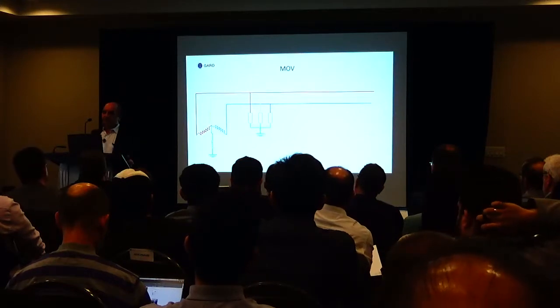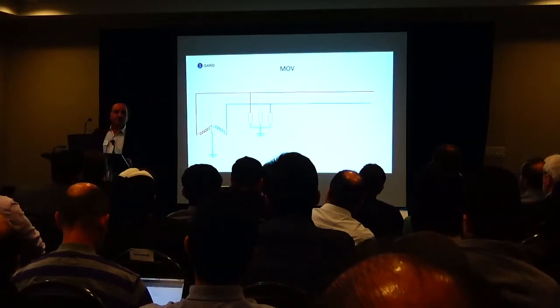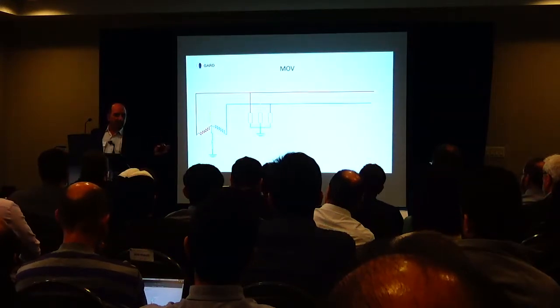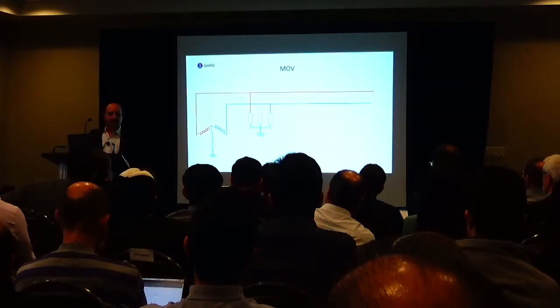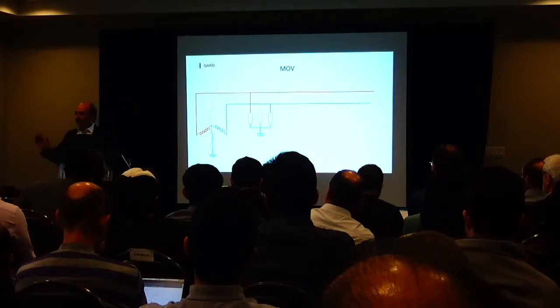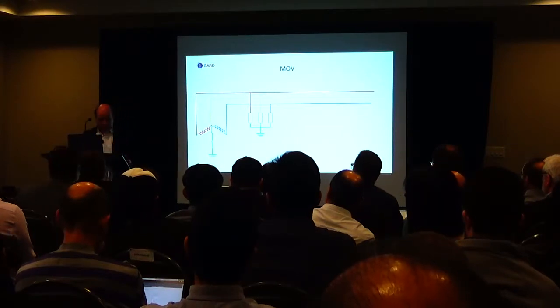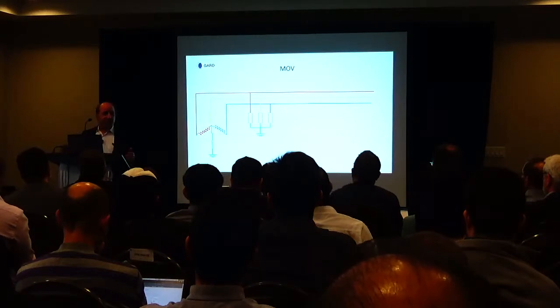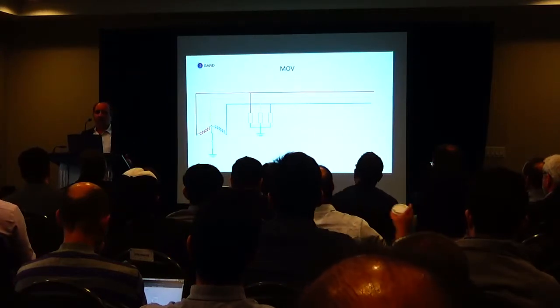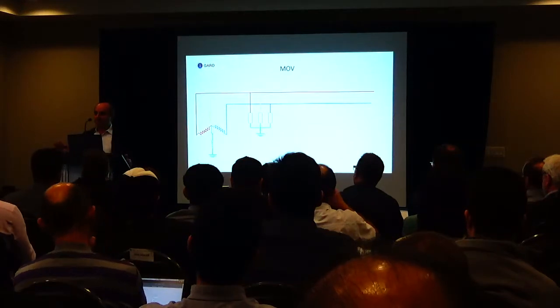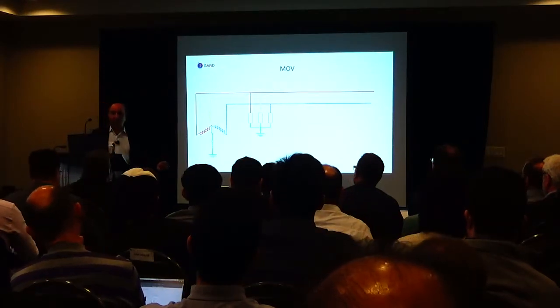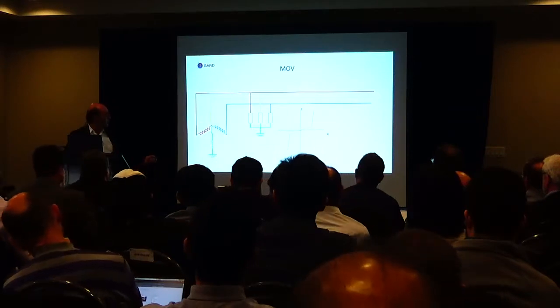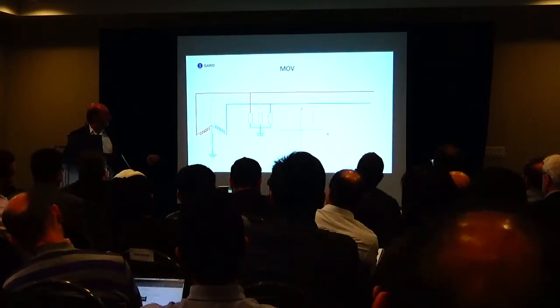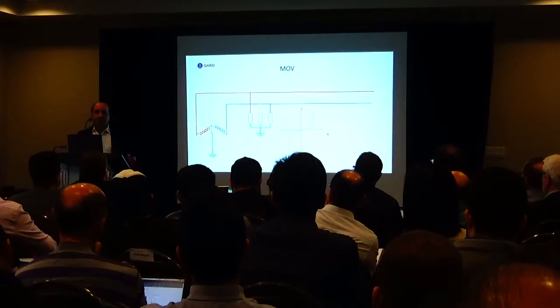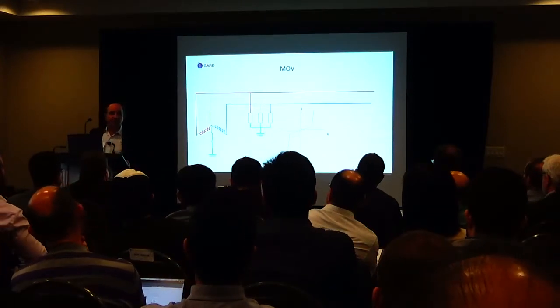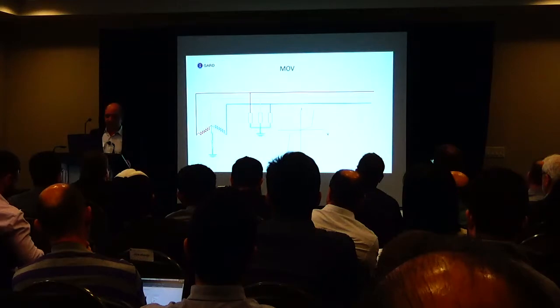And we had a facility in Toronto, a data center, that changed their entire system from solidly grounded to resistance grounded, and they hired an electrical contractor or an engineering firm to go in there and do all this. And engineers are great because they think that if one surge protective device is good, 100 must be better. So what happens when you get a ground fault and you have a surge protective device? A surge protective device is an MOV, and this is the curve, voltage versus current, showing the current going through the MOV.